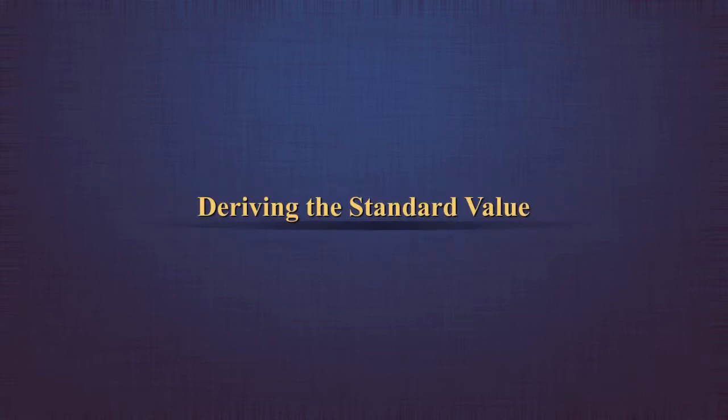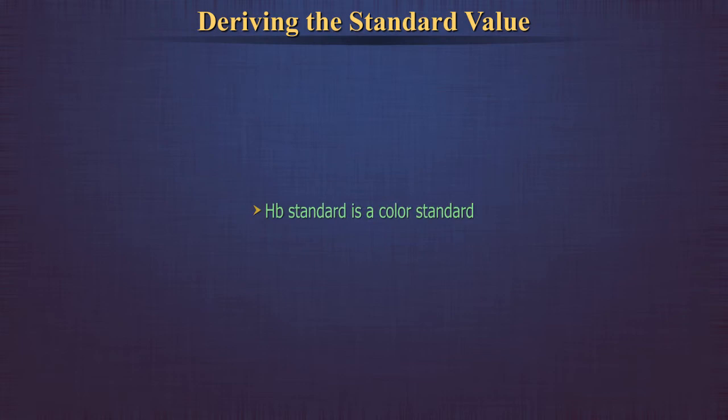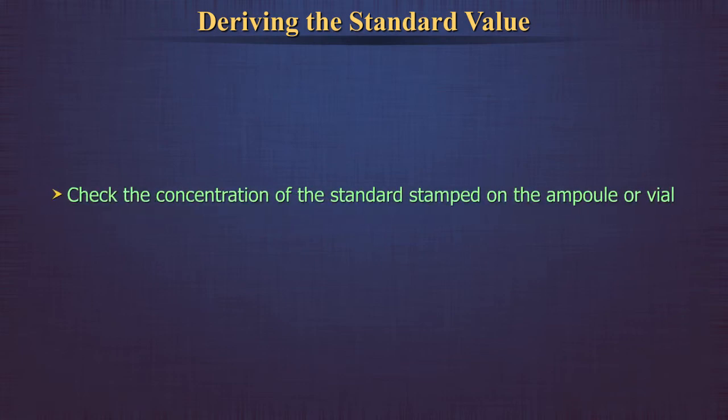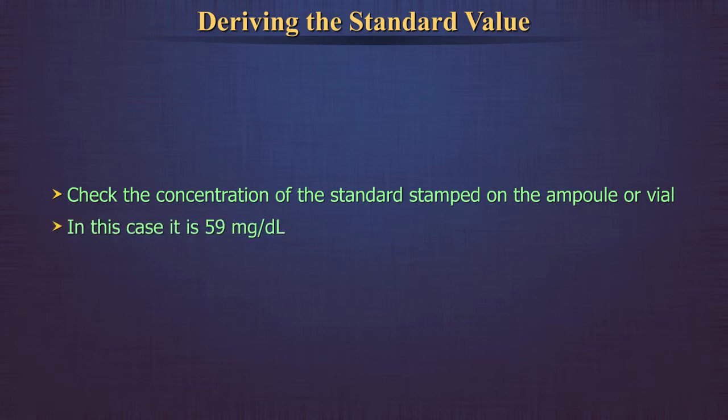Deriving the standard value. Hemoglobin standard is a color standard. Check the concentration of the standard stamped on the ampoule or vial. In this case, it is 59 mg per deciliter.